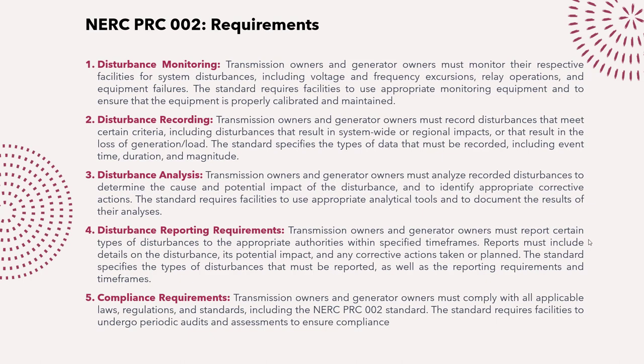Disturbance monitoring covers system disturbances including voltage or frequency excursions, relay operation, and equipment failure — all of which should be recorded. The standard requires facilities to use appropriate monitoring equipment that is properly calibrated and maintained. These monitoring facilities should be able to record such disturbances, and those recordings should be properly maintained, capturing the entire event to support proper root cause analysis.